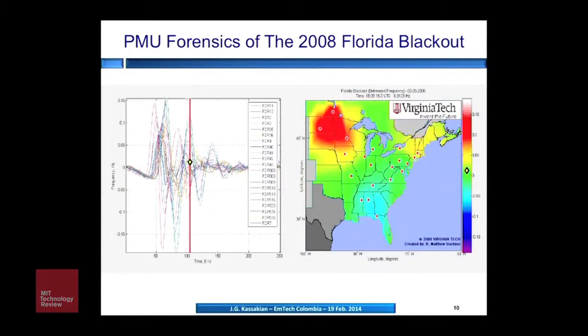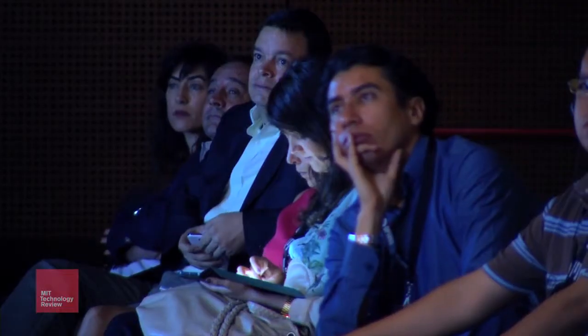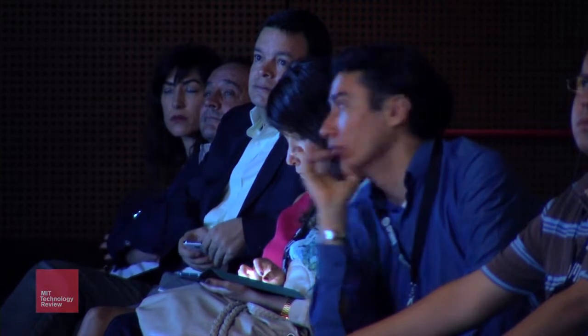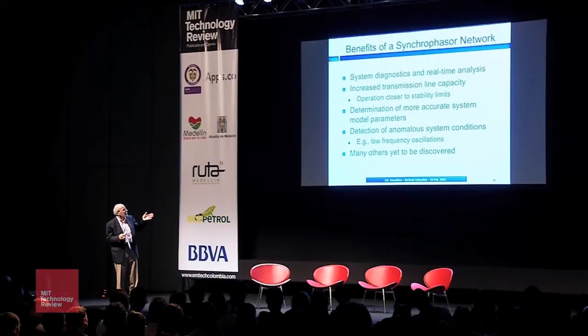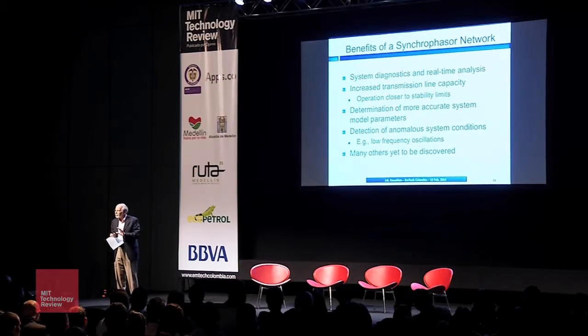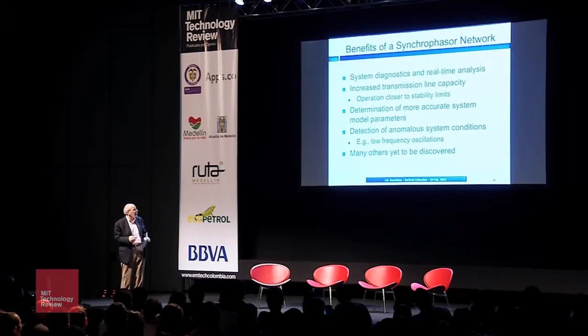And what you see there in the colors is actually the variation in the frequency from 60 cycles caused by the problem down in Florida. And that is possible to see because of the presence of those phasor measurement units. So what can we do with the synchrophasor network? Well, for one thing, we can tell exactly what's going on with the network at any time, and because we can see that, we can anticipate problems and provide a solution before they become catastrophic.